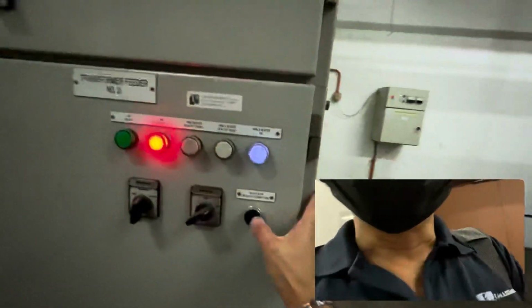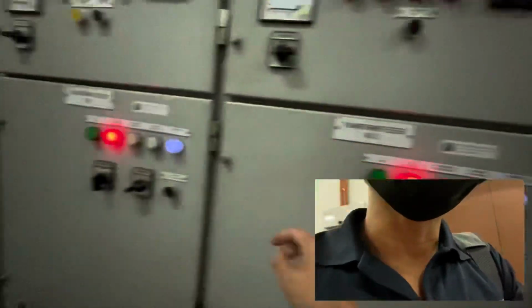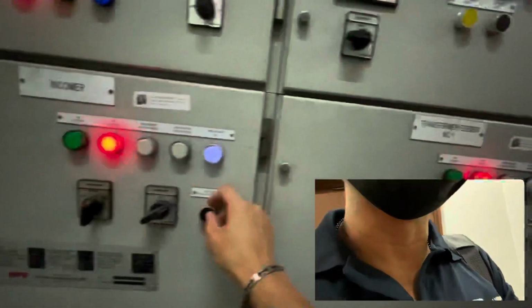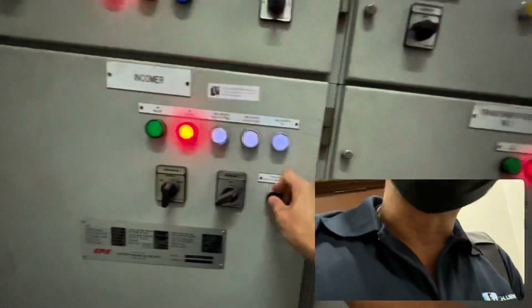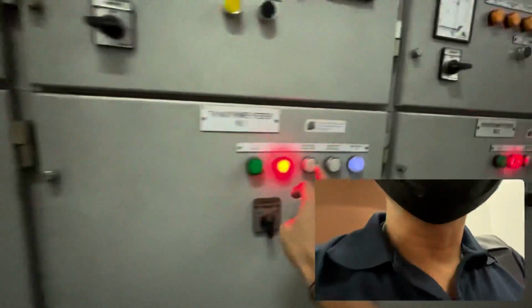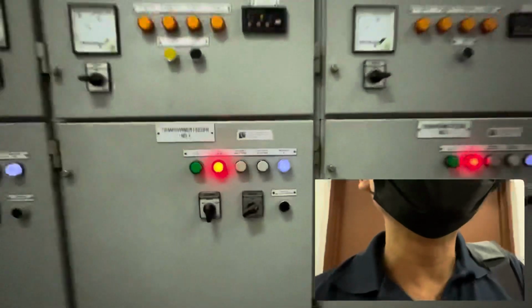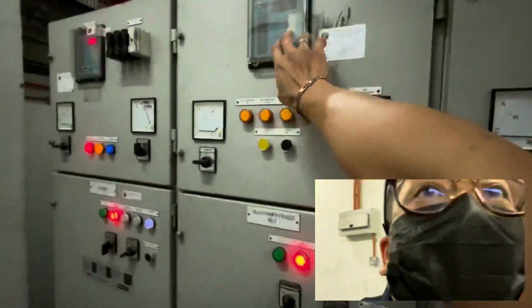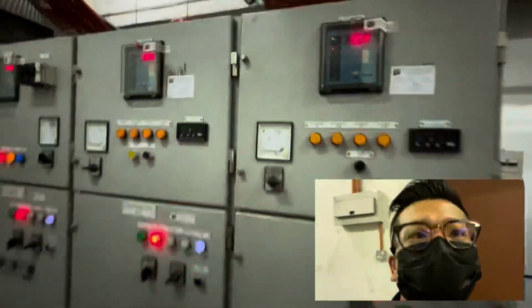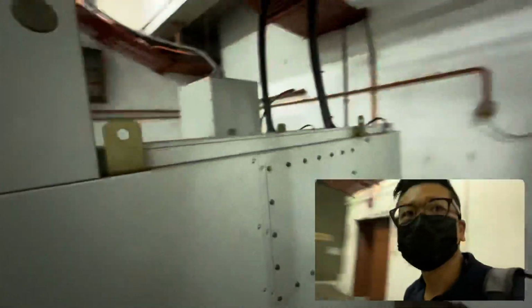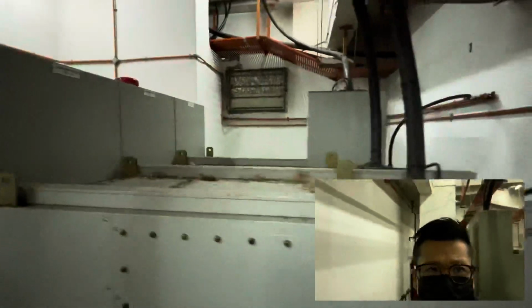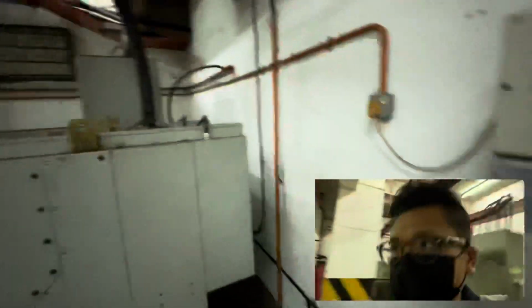Alright, here we have the heater testing switch to know the heater is in good condition. However, you can check the current for the heater in order to know more accurately. Protection relay is in good condition. Okay. Panel is quite dirty, need to do servicing.